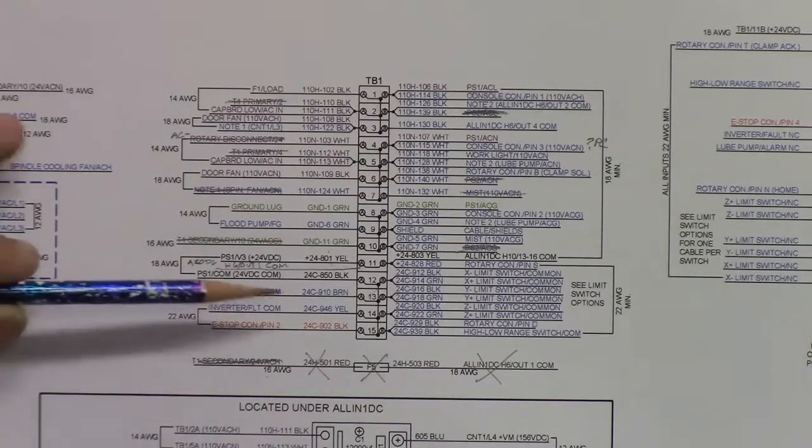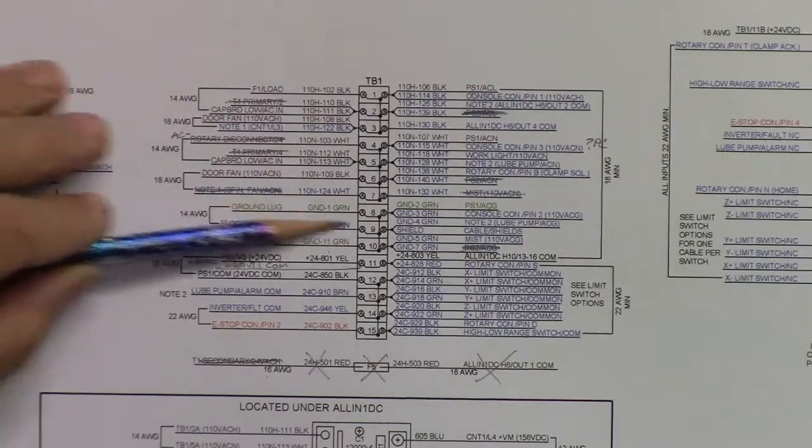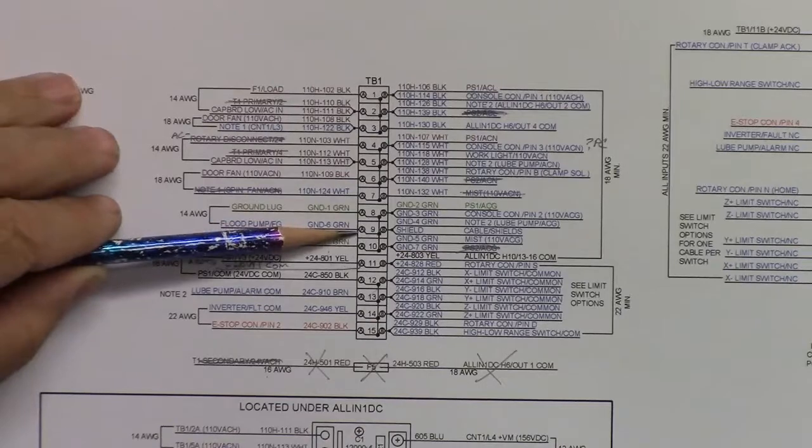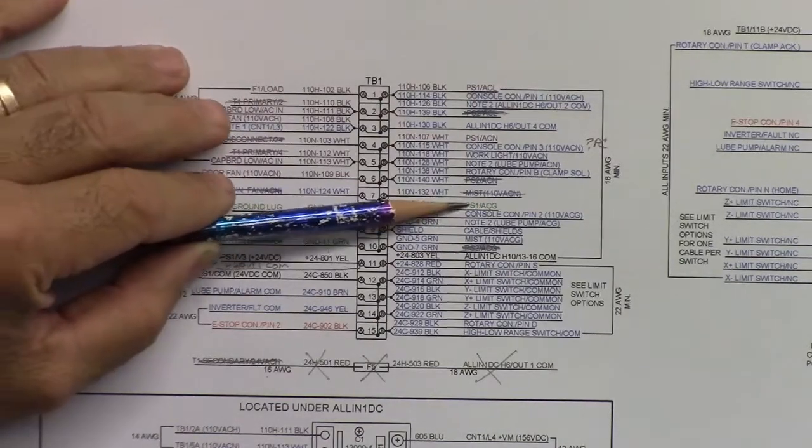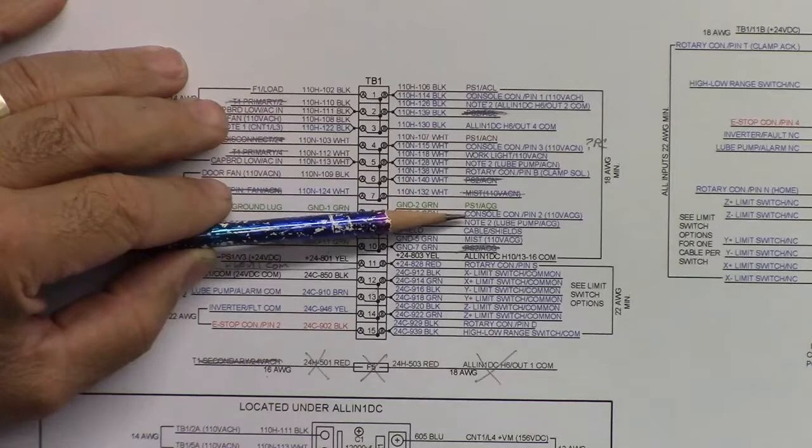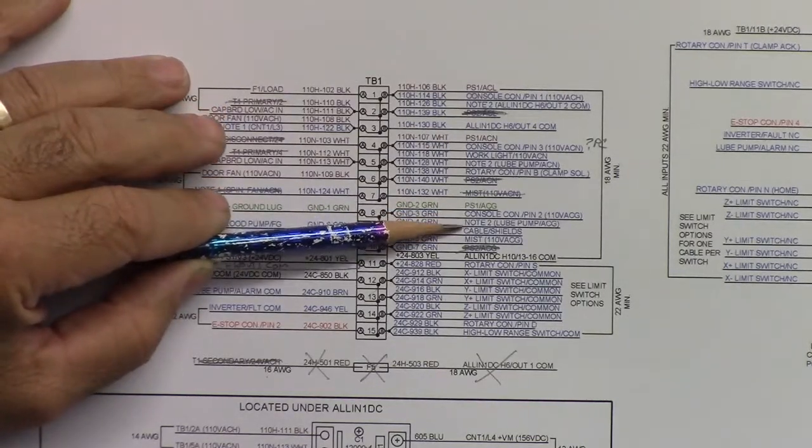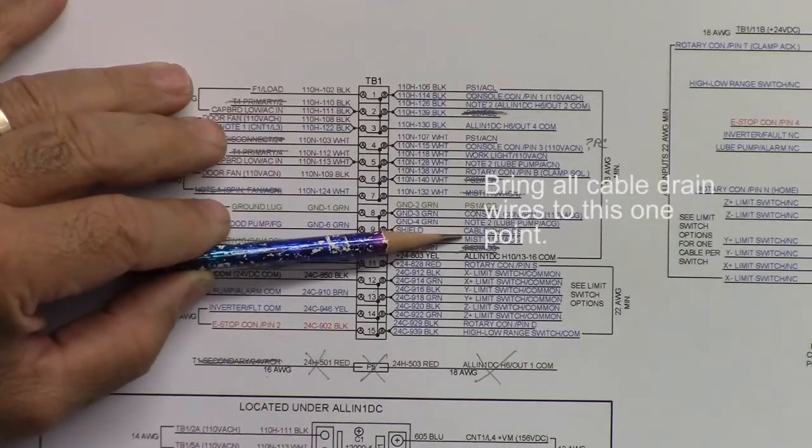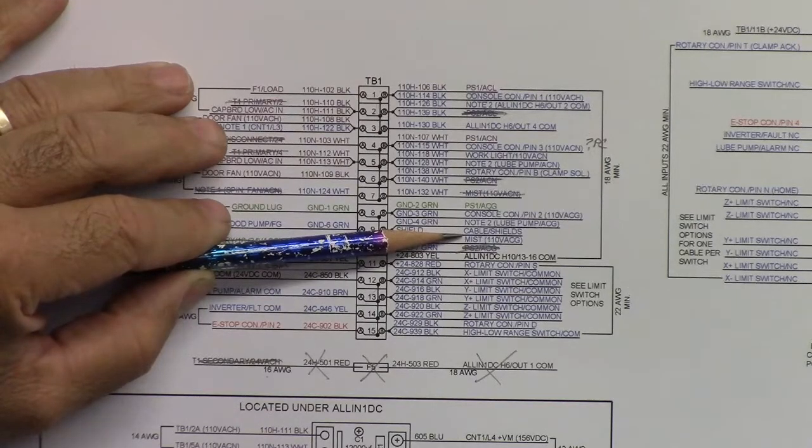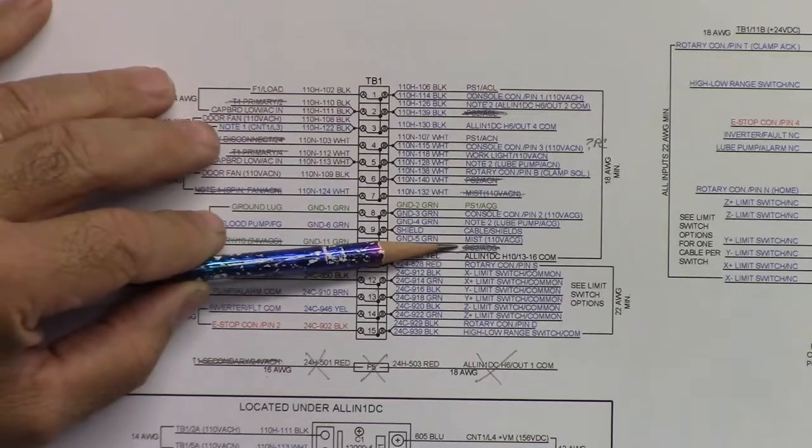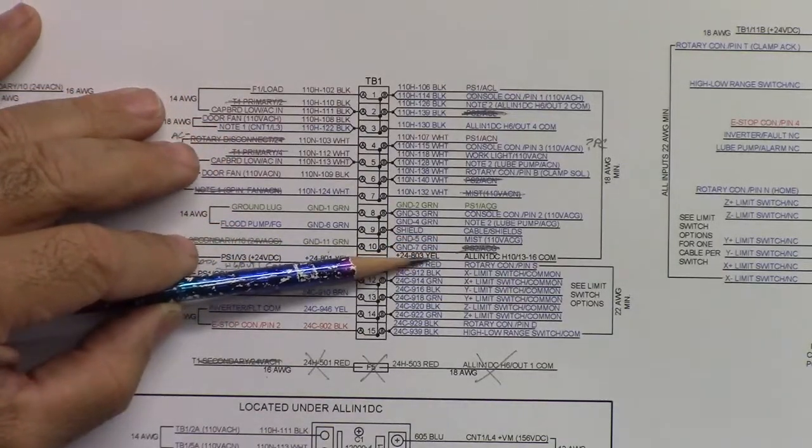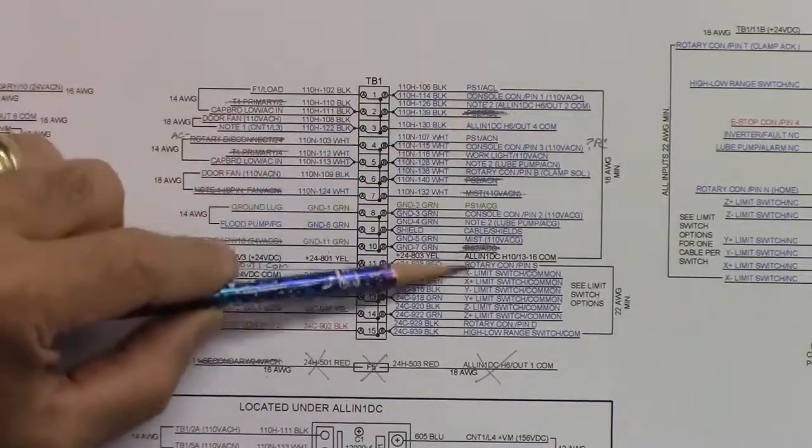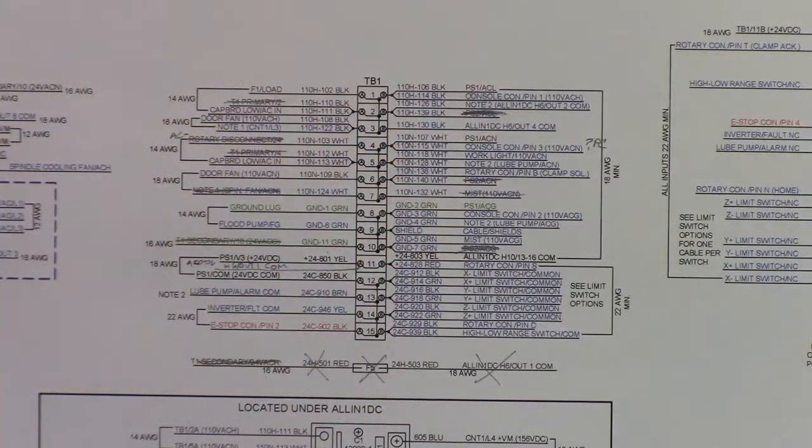On this side here, we got rotary con pin clamp. I'm not sure what this is. I have to look it up. Here's the lube pump neutral, work light neutral, console neutral, power from the console. And then this is the neutral for the power supply that feeds the all-in-one DC. The next one we have here, these are all just the chassis grounds. We've got a ground lug for the cabinet, and you've got a flood pump ground, power supply ground. That's PS1. Again, that's the power supply for the all-in-one DC. Console ground, lube pump ground, all your shields. If you have cables with shields in them, and they have a drain wire, they're all going to come into this cable shields. Mist, if you have a mist system that has a ground, it comes in here.